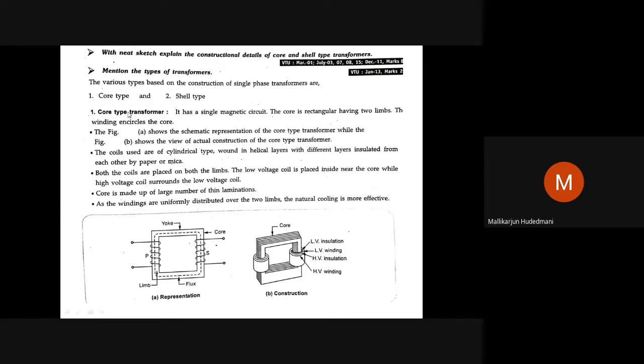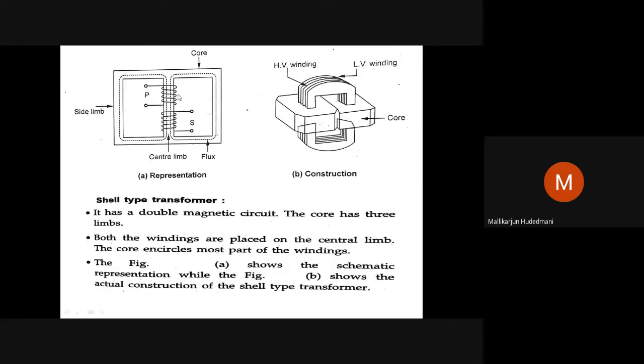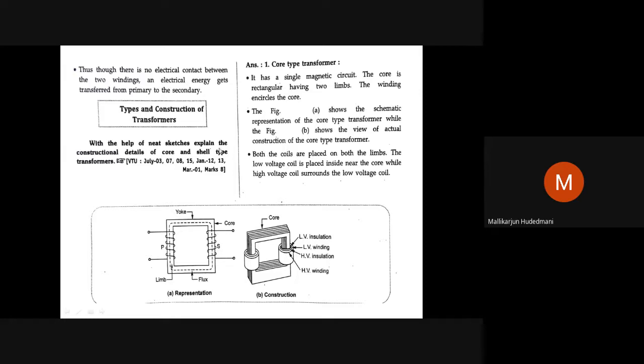Then classification of transformer: core type and shell type. You can see here, this kind of rectangular frame and windings are put on the limbs. Vertical sides are called limbs. Horizontal sides are not used for windings. Windings can be concentric, one inner assembly, one outer assembly, like bobbin type: low voltage and high voltage sandwiched. If we have a considerable part of the core surrounded by the winding, we call it core type. If considerable part of the winding is surrounded by core, we call it shell type. Here is the shell type. You can see core is around the winding. Definitely we have three limbs. Only on the central limb we have windings.